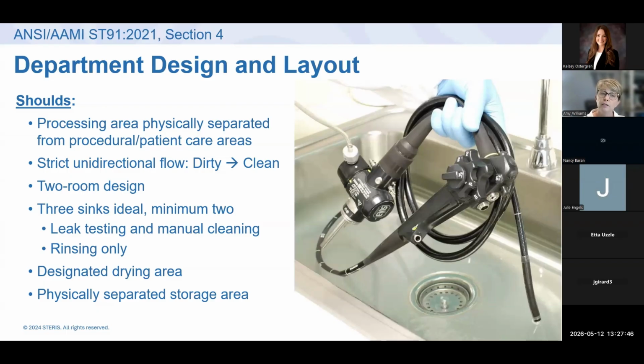But very clearly, there are some requirements for your physical layout. One, there has to be a strict unidirectional flow from dirty to clean. I know that makes sense, dirty to clean, no backtracking. The hard part about that in endo is that a lot of times once you get from decon into the clean work area, there's no way to get out of the clean area without going back through decon. People don't think a lot about that because they don't see scopes as always sterile, so they don't think it's that big of a deal, but it is. If you've cleaned that device, taken it out of the AER, dried it, whatever, you shouldn't be going back through decon. So if that's an issue for the layout of your area, it definitely warrants conversation with admin about how we can do it differently.